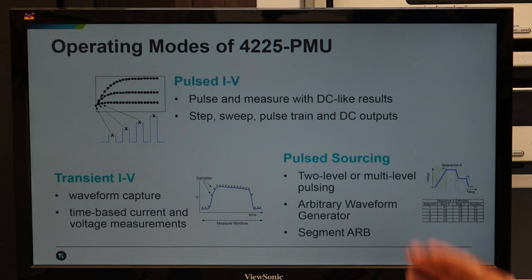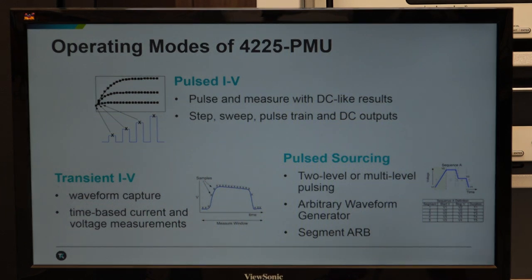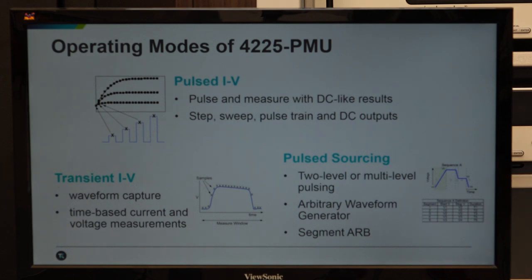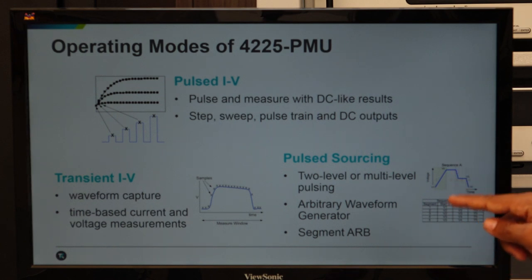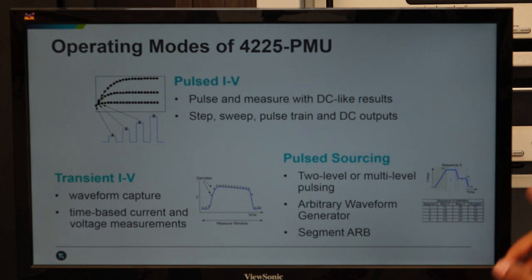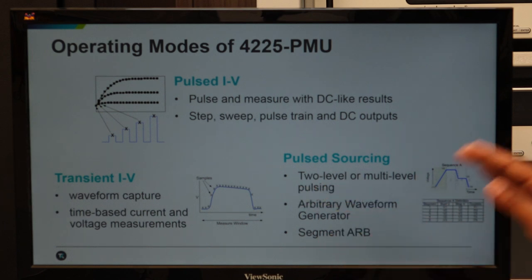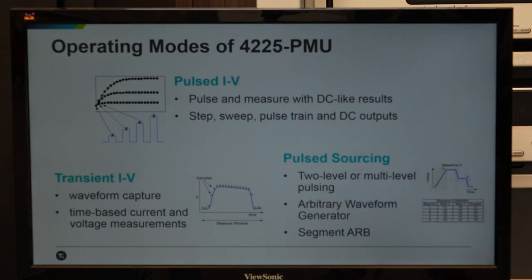The third aspect is arbitrary waveform generation or multi-level sourcing, where two-level amplitude with different rise times need to be applied. Applications in memory testing, reliability testing, failure analysis, and device lifetime testing require applying non-standard waveforms. This kind of segmented or arbitrary waveform generation is supported equally with current and voltage measurement via the digitizer. With these features, this particular instrument is very useful in advanced applications.